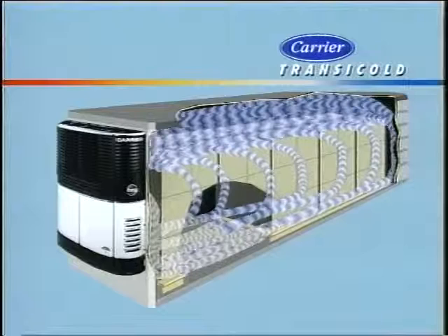Now that we've become familiar with the unit and verified there is fuel in the tank, we can start it up. Let's take a look at page 4 of the operator manual. First, we'll place the Start Run Off switch in the Start Run position. The microprocessor will turn on all the indicator lights first, then the LCD segments in the main display, and black boxes in the message center. This will last for 5 seconds while the microprocessor completes a self-test.